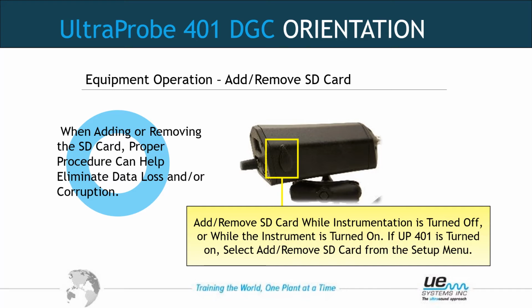So there's only 2 ways you should take the card out of the unit. When the unit is completely powered down, you can then remove the SD card. Or you can go to menu item number 1 and choose it again by holding a little longer on the sensitivity dial, and it will tell you safe to remove SD card, and then it will ask you to put one back in. Once you put one back in, that screen will disappear. Those are the only 2 safe ways, so we don't mess up any kind of software information or firmware information.